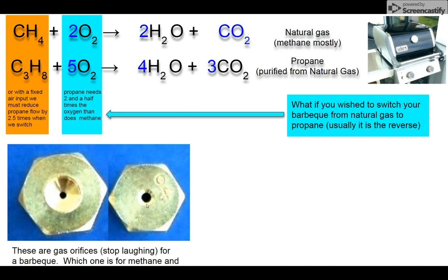So can you tell me which of these inlets allows you to use methane and which one lets you use propane? Well, if we can't change our air, then the propane machine must use two and a half times less propane to balance this equation. So that's the propane orifice. That's the methane.